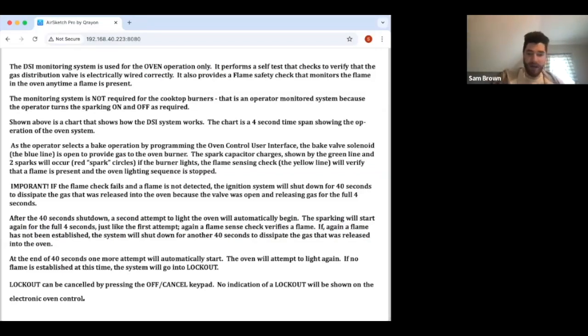It wants to wait for any gas that was released to dissipate. Then it'll try again. If nothing, off for another 40 seconds. It tries a third and final time. And if it fails to establish a flame then it goes into a lockout mode, which there's no indication of on the control. It just goes into lockout until you press off or cancel on the keypad.